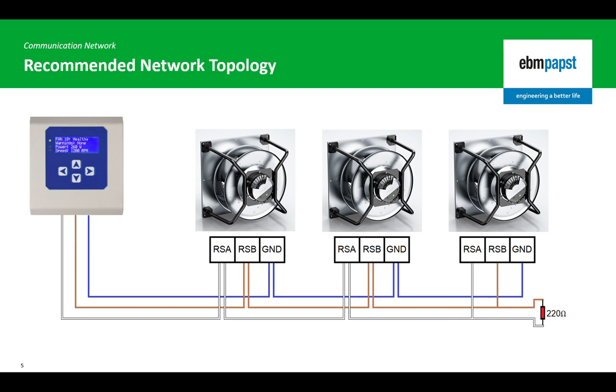Stub or star networks with one central connection to the controller are not recommended. At each end of the network, there should be a termination resistor fitted to dissipate the energy of the signals passing through it. This is usually included in the communication circuit of the client controller, and requires the customer to ensure that a similar value resistor is installed at the end of the network at the last server device.